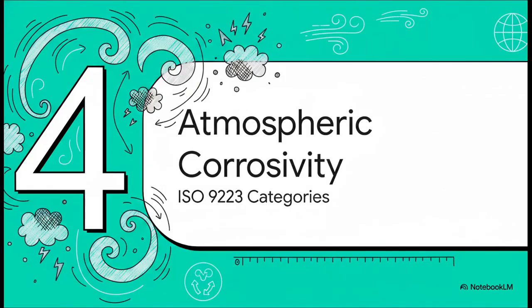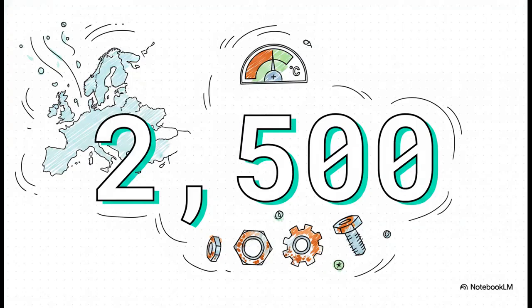All right, so we've talked about the boxes, the enclosures shielding our motors and drives. But what about the actual air wrapped around those boxes? Let's zoom out a bit in Section 4, Atmospheric Corrosivity Categories Explained. I want you to just think about this number for a second: 2,500. Any idea what that is? That is literally the number of hours every single year that massive parts of Europe spend sitting at over 80% relative humidity with temperatures above freezing. That's enough time to cause some serious damage.